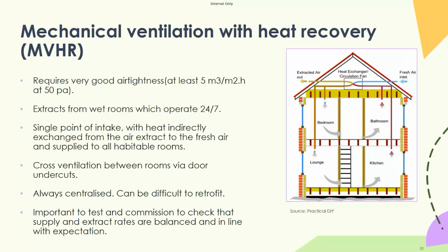So you've actually got both an inlet and an outlet in the loft space, or from an airing cupboard or similar to outside, and you're passing that incoming air over a heat exchanger and filters, preconditioning incoming air to living spaces and bedrooms, and then having the extract serving your wet rooms again.